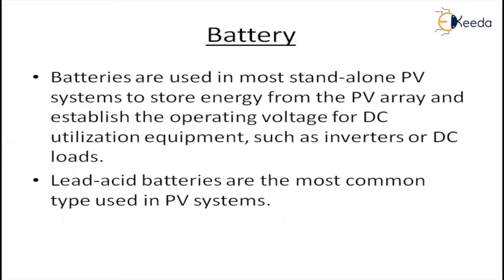The first part is a battery. If required for standalone systems, battery is the most important element to store energy, because PV is not available at night. For storage purposes, we use a battery. Mostly the batteries used in a PV system are lead-acid batteries, and for lead-acid batteries the depth of discharge (DoD) is 50% for design. You want to maintain it as a maintenance battery, though sometimes maintenance-free batteries can also be used.